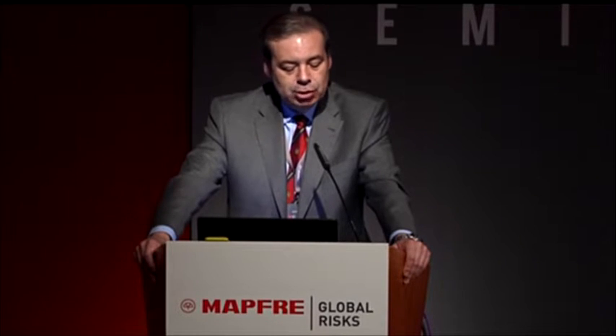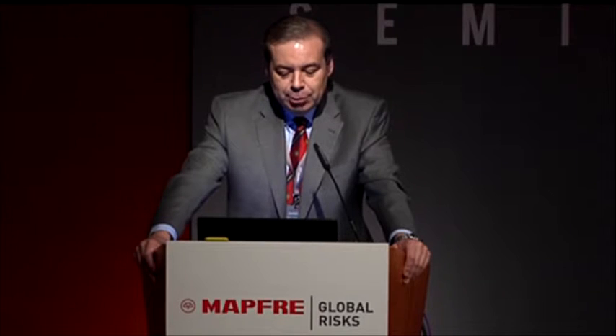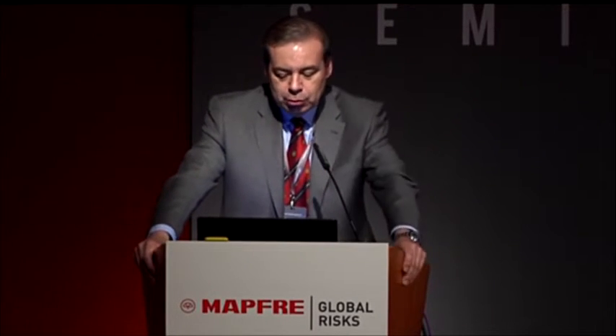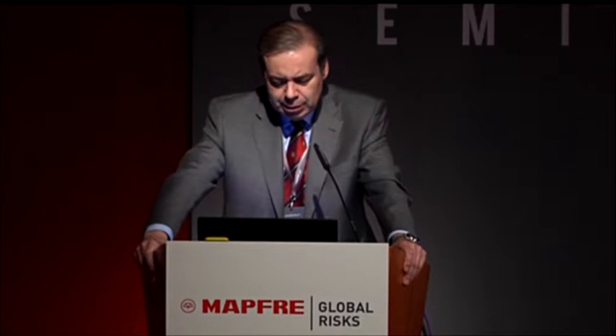Let's take a look at the third degradation phenomenon: stress corrosion cracking, or SCC, that occurs when there's a combined action of a corrosive agent, polluted moist steam, and a mechanical effort. I'd like to clarify something not specified in my presentation, which is that stress corrosion cracking is often caused as a result of the steam becoming polluted.